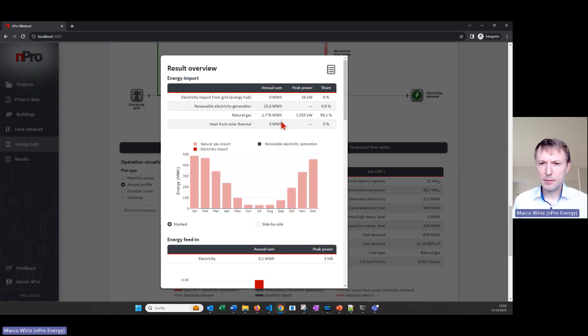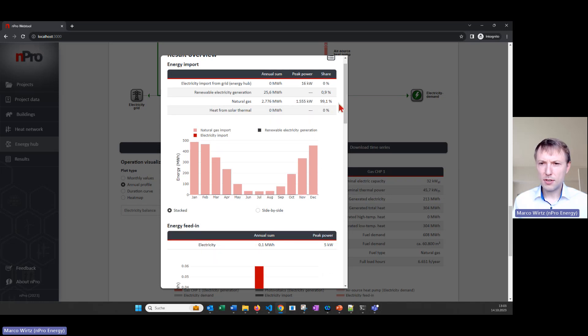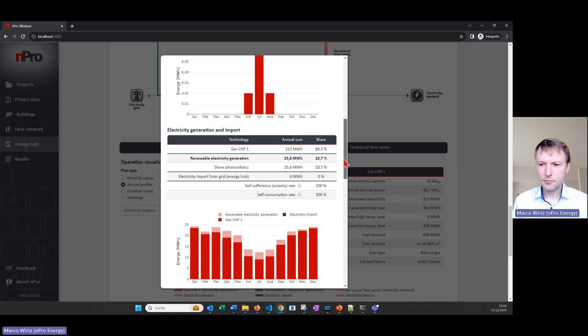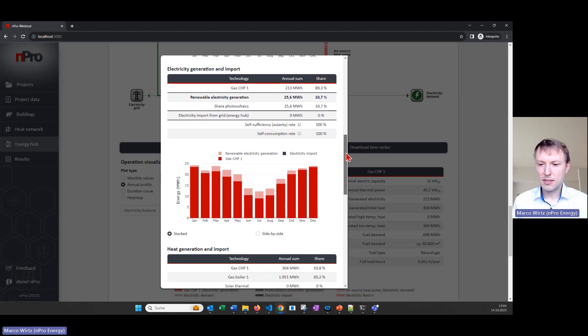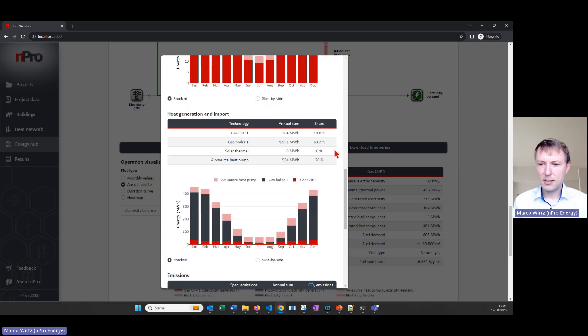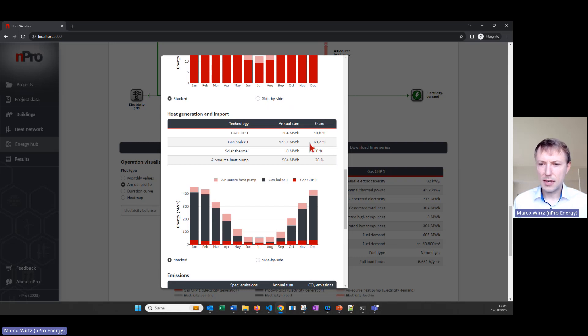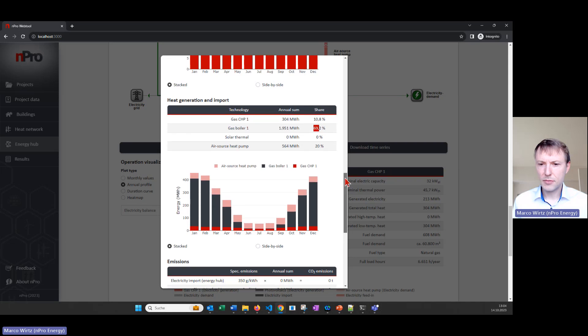We can also click on 'Summary' and there we get the most important KPIs of the system — how much energy we import, most of it being natural gas but also some renewable electricity generated on site. We see KPIs regarding the electricity, and here we see that all of the PV power can be used directly by the system itself. Here we see the different shares of the heat generation units: the CHP is covering 11 percent of the heat demand, the gas boiler 69 percent, and 20 percent is covered by the air source heat pump.